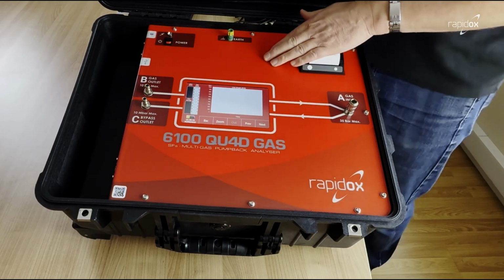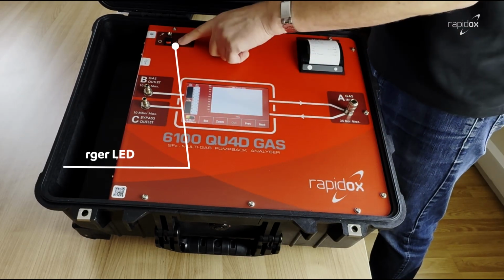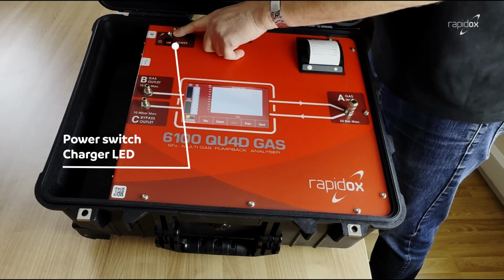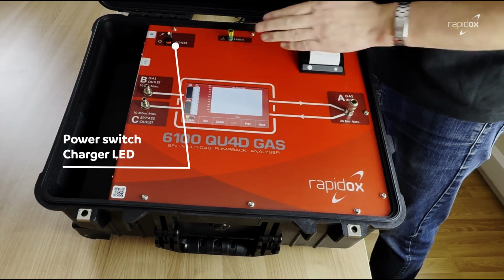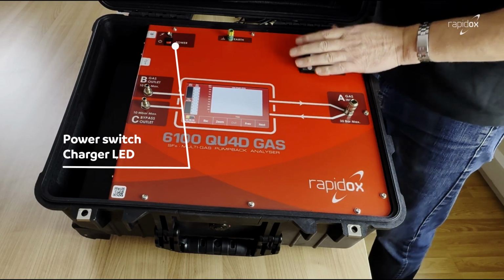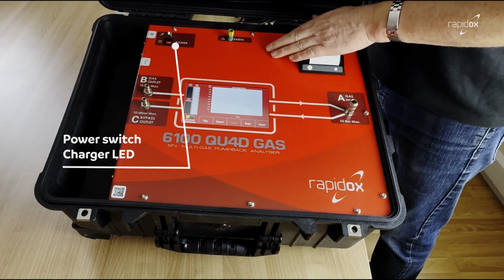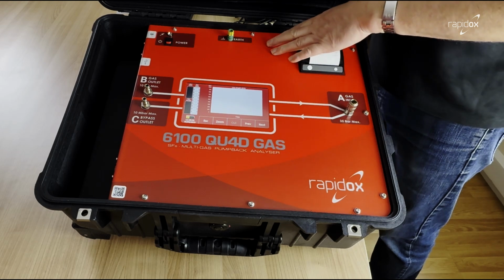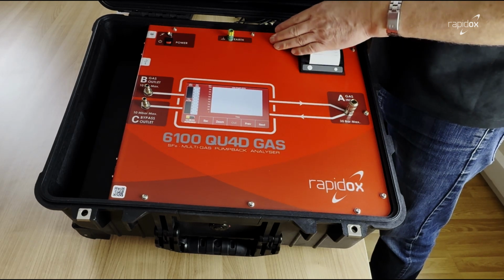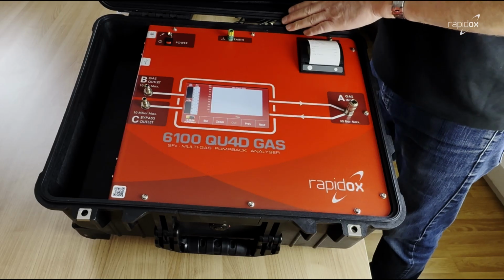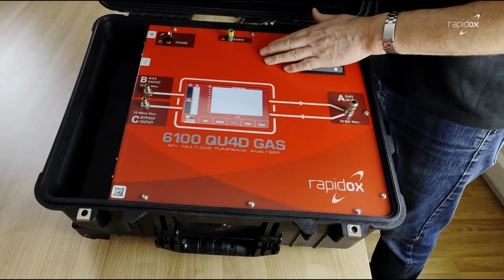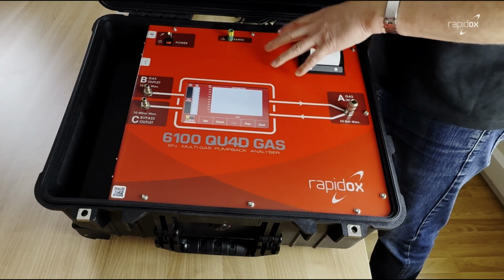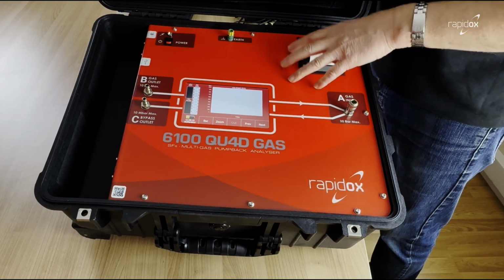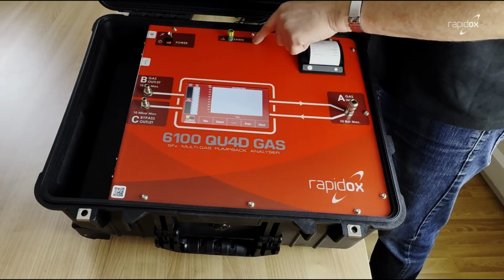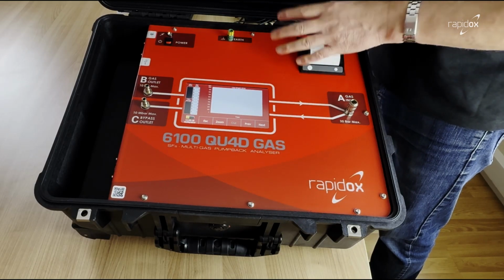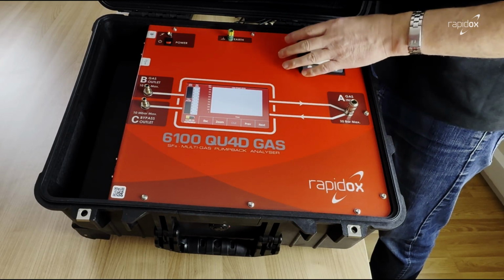Now, moving around the analyzer, on the top we've obviously got the power switch and we've got a charger here. Now the analyzer is running off batteries, as you can see. There's no charger on here at the moment. The analyzer is charged using a charger cable which we supply with UK, EU, USA, Australian plugs for adapters, and you can operate this machine either on battery or on mains. It doesn't matter. When it's on mains, the battery is being charged while you're operating the equipment. It works exactly the same way as a laptop computer.